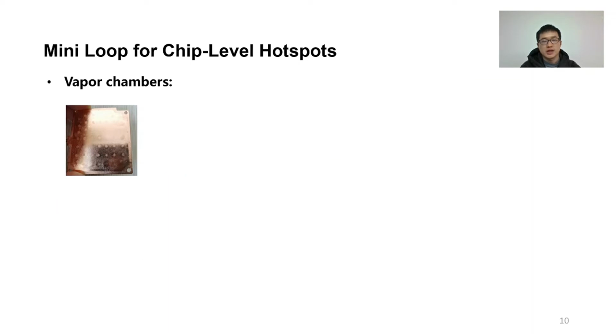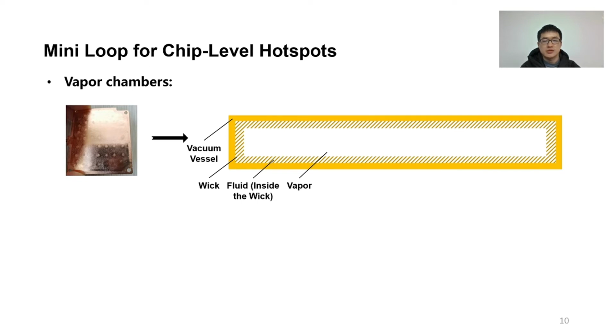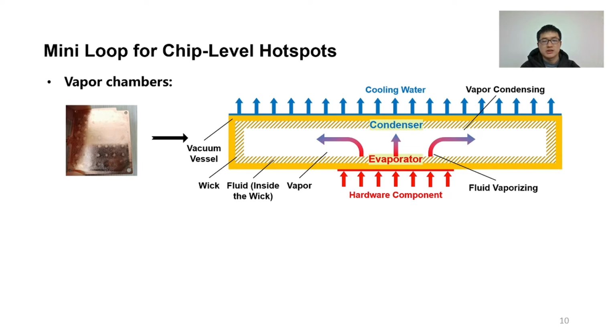The mini loop is designed for solving the chip-level hotspots with vapor chambers. The vapor chamber consists of a sealed vacuum vessel and an internal wick structure. The wick structure contains a small amount of fluid in equilibrium with its vapor to transfer heat from one side of the chamber to the other. When a hardware component attached below generates heat, the fluid absorbs the heat and immediately vaporizes and rises to the condenser, driven by the pressure difference. Once arriving at the condenser, the vapor condenses again and releases the latent heat of condensation to the cooling water. The condensed fluid finally returns to the evaporator.